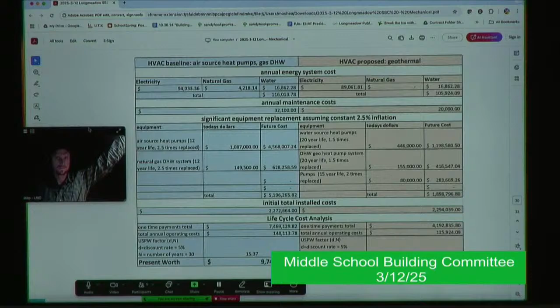The circulator pumps for the facility see 15 years. Again, some pumps last 30 or 40 years, but the industry assumes 15 years. Those have redundancy though, so if one fails you just swap it out or repair the motor or component. The ERVs and AHUs are some of the bigger components, typically with a 20 to 30 year life expectancy as well. The ERVs realistically can be repaired in place for a lot of their components. The boxes can last over 20 years, and it's really just replacing fans as they fail, and maybe damper blades and the energy recovery core.